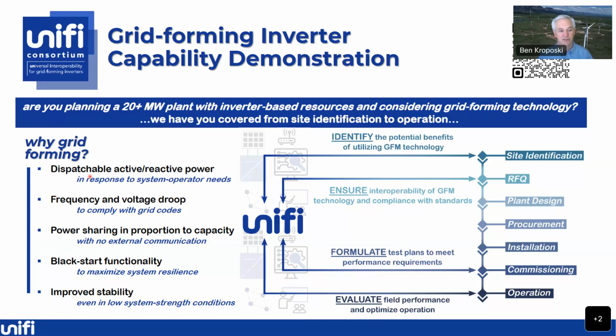So we want to look at how well we can do real and reactive power dispatch. How well do the things respond to voltage and frequency droops? How do we do this power sharing amongst all these different devices? Additional capabilities would be to look at black start capability to maximize system resilience and improve the overall stability of the grid at high levels of inverter-based resource deployment. So again, we're really interested in looking at these larger scale deployments, and we have a couple that we're investigating right now, but we're looking for more examples, especially in the United States, where people are considering these large scale grid forming inverter technologies.